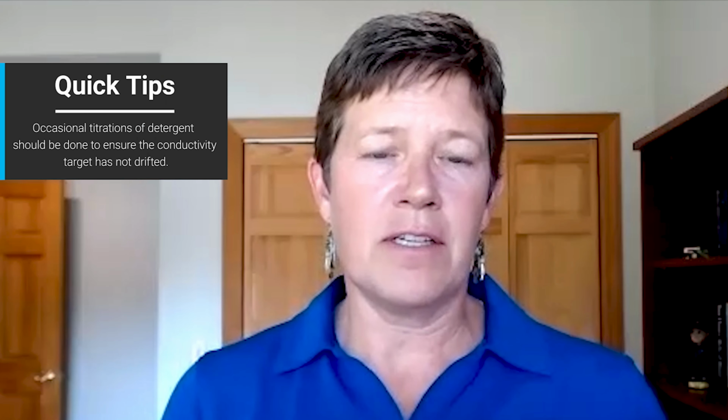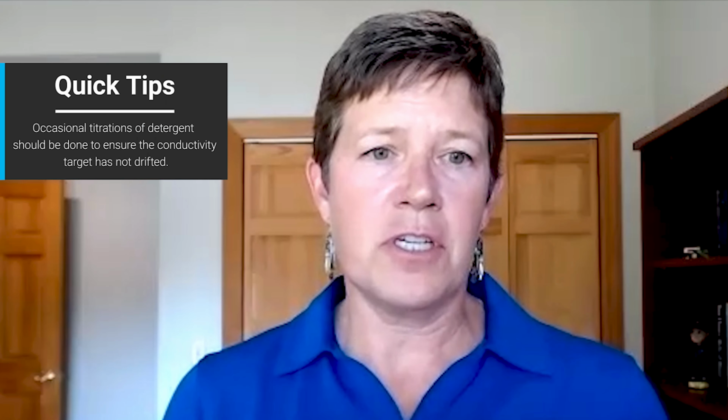Yeah, thank you, Pete. It's important to monitor the operating parameters to make sure that you maintain the validated state. So we can work with customers to set up ongoing monitoring of temperature, detergent concentration, and timing in the cycles, and even occasional titrations of the detergent concentration to ensure that the conductivity target hasn't drifted. We can also help structure the validation program. If it's set up effectively, equipment groups and product groups will be defined in a way that new equipment and new products can be introduced without a major upset to the validated state. And when we find that a new worst case, really tough to clean product is introduced, or a unique piece of equipment is added into the cabinet washer, it's pretty easy to add recipes and amend the validation, the way that Sani-Matic's done the recipe builds. So definitely, we're there to help going forward.